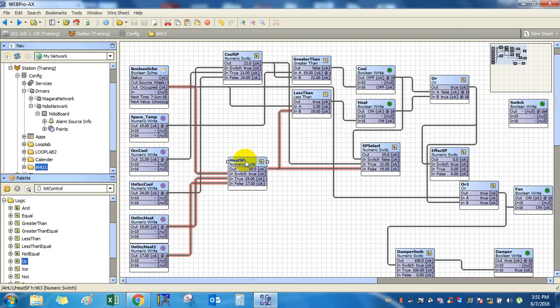So this one helps me choose which one. So here I compare greater than. Here I come to know whether I have to cool or not. If this says I have to cool, I come here and I choose the true value of cooling. Else I still provide the heating set point. I have to provide only 1 set point to my system. 1 effective set point, right? Make sense? There has to be only 1 set point effectively for the space.